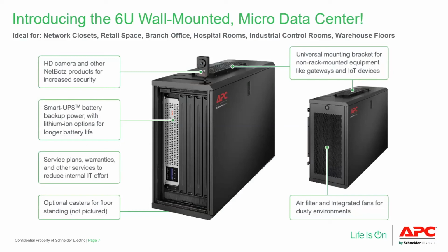This mounts vertically on the wall, which is different from a lot of our competitors' wall mount cabinets that have very high depth—this one is very low depth. The UPS, as you can see, is mounted vertically, and it's very easy to integrate. We can integrate this with a power distribution unit, that lithium-ion UPS you see there, along with a security camera at the top of the rack to ensure that any non-IT staff who might have access to that room—maybe a healthcare clinic with a patient in it—can't easily reach it, since it's mounted high enough, and it also has HID access security.